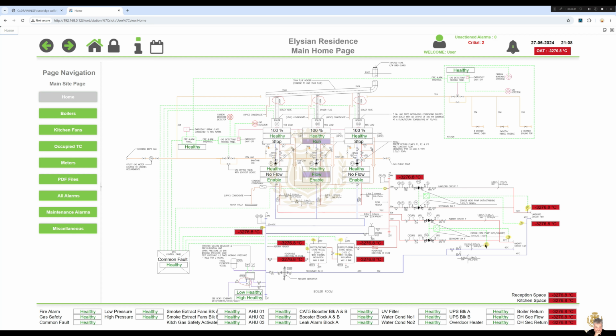But apparently I've been told now that they want a supervisor, a head-end supervisor, so I can either copy these graphics onto the supervisor or just use a supervisor to navigate to this controller, but use a supervisor to bring in the histories and put them as unlimited so they can monitor it for years, which we can't do as it's just on a station because it won't store that much.